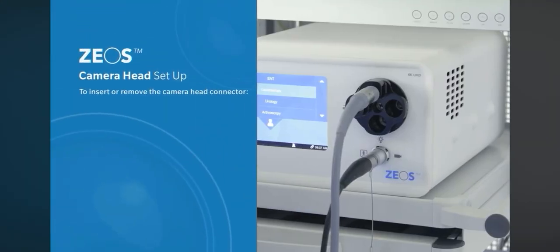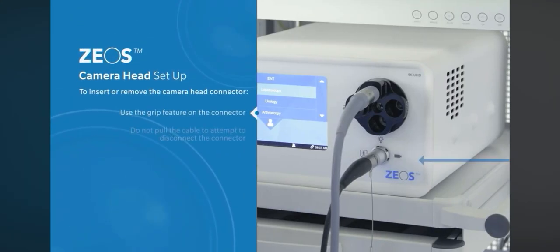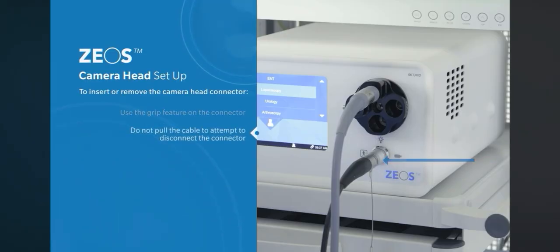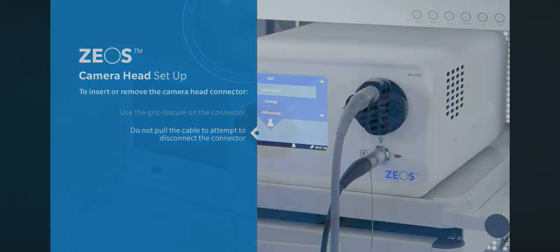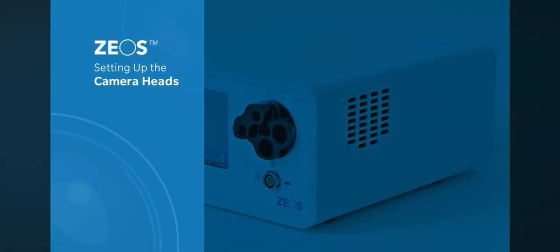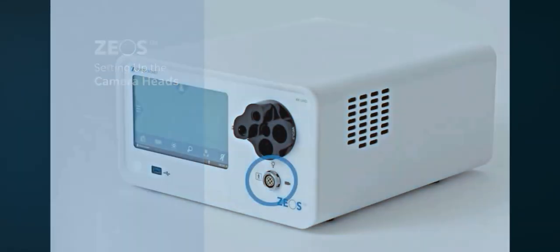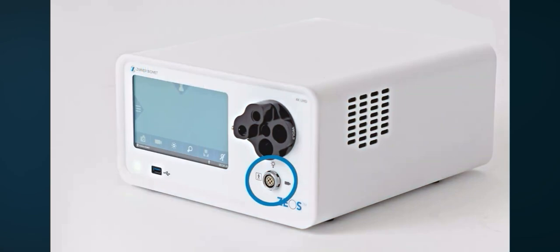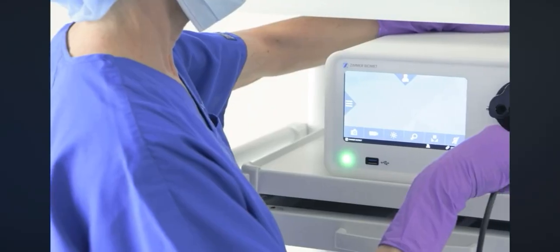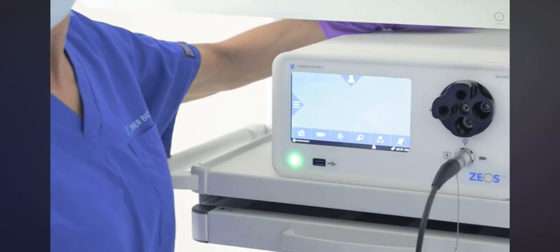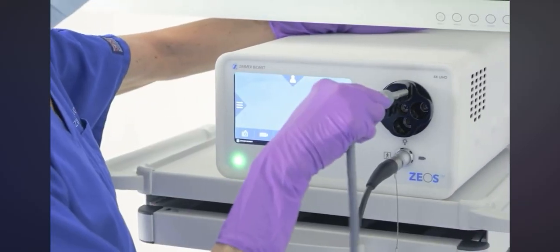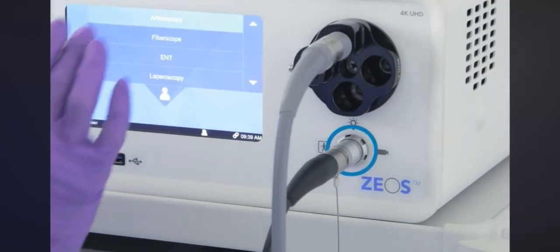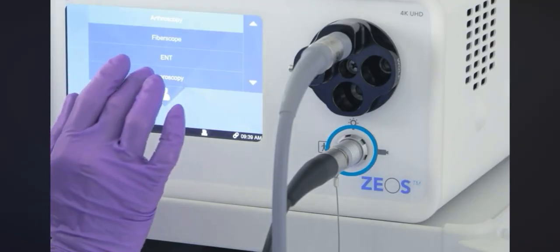To insert or remove the camera head connector, use the grip feature on the connector. Do not pull the cable to attempt to disconnect the connector. Insert the camera head connector into the camera receptacle on the front panel of the Zeos console. Alignment marks are provided on the camera head connector to ensure proper orientation. Make sure the camera head connector contacts are clean and dry prior to insertion.